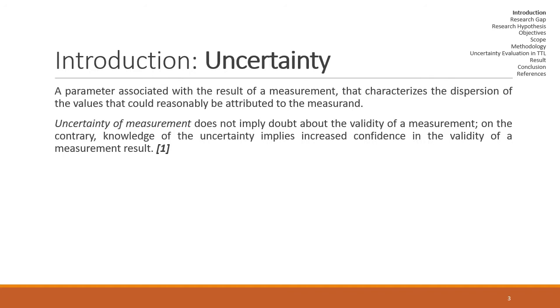Uncertainty evaluation is essential to guarantee metrological traceability of measurement results and to ensure that they are accurate and reliable. In addition, measurement uncertainty must be considered whenever a decision has to be taken based on measurement results, such as accept or reject, or pass or fail processes. Regardless of how careful or scientific, all measurements are subject to error and uncertainty. We can never be absolutely certain that a measurement result is true or final. Therefore, we must establish a boundary within which we are confident that the measurement result will lie. Therefore, uncertainty of measurement does not imply doubt about the validity of a measurement. On the contrary, knowledge of the uncertainty implies increased confidence in the validity of the measurement result.